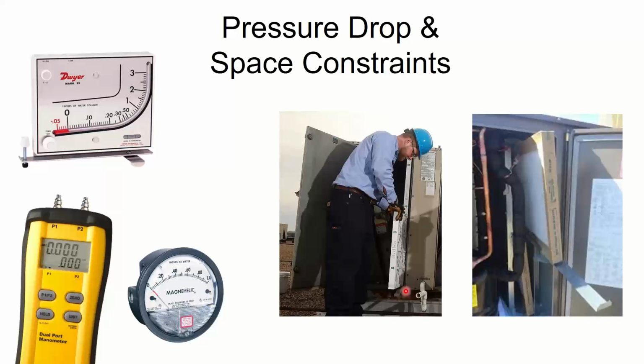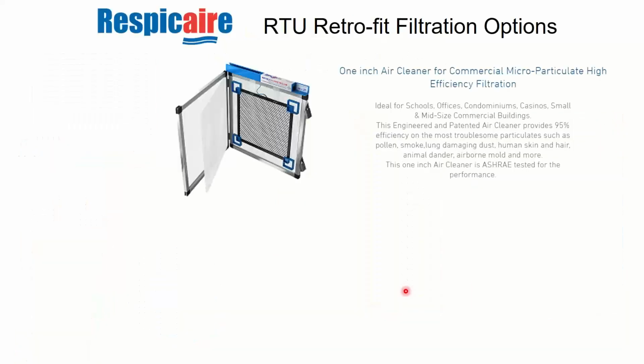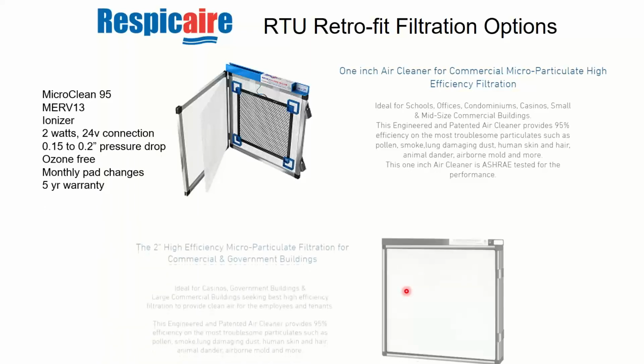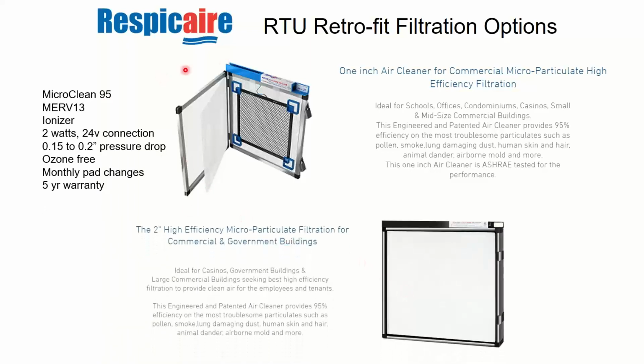So your options for upgrading filters are challenging because generally speaking, the higher the Merv rating of the filter I put in, the thicker, the wider it's going to get. So instead of 1 inch, I'm going to have to put in something that's 3 or 4 inches in depth in order to get good filtration. And that's a problem. I don't have the space to do it on a rooftop unit. So because of that, we have solutions for that. This is one of those solutions. Like I said, there's many things going on here, but this one can come in a 1 or a 2 inch width scenario. We call it MicroClean 95.